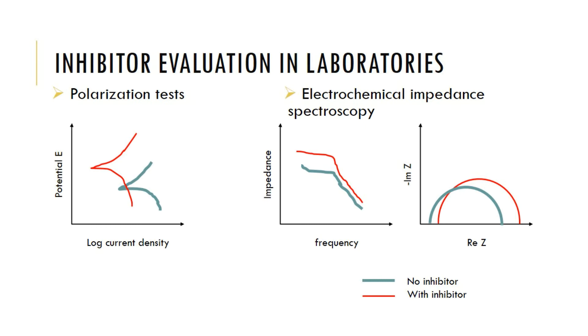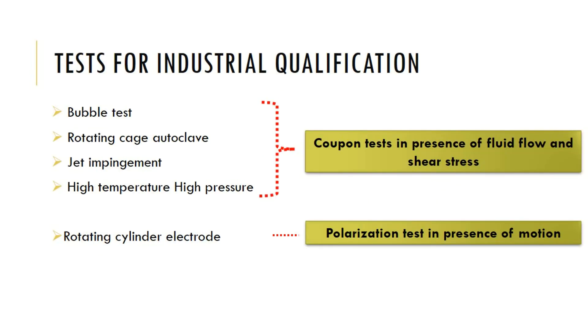Such electrochemical polarization testing may not always be done when inhibitors are qualified for use in an industrial environment. The typical tests for industrial qualification usually include bubble test, rotating cage, autoclave, jet impingement, and high temperature high pressure tests. These four are coupon tests where corrosion rates are measured, but the rates are measured in the presence of fluid flow and shear stress, taking into account fluid flow that happens in the internal regions of pipelines or similar equipment.